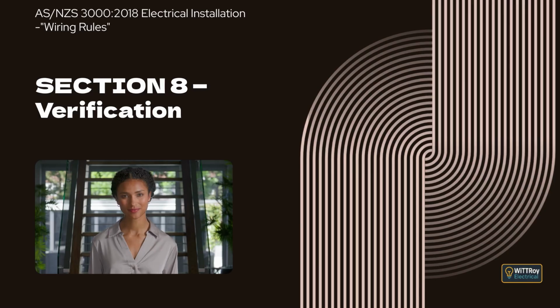Clause 8.3.3.3, Test Failures. This clause explains that if any part of the electrical installation fails a test, that test and any earlier tests that may have been affected by the fault must be repeated after the fault has been corrected. This ensures that the installation is fully compliant after rectification.